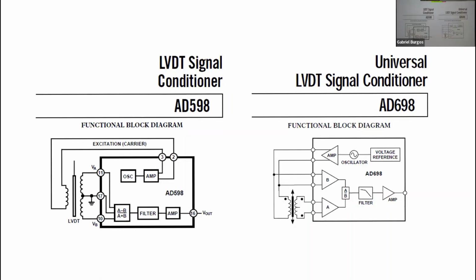So they claim it'll work for any LVDT. My experience with people in the field is that it works up to a reasonable temperature limit, but after you get past about 60 degrees C, you've got problems.